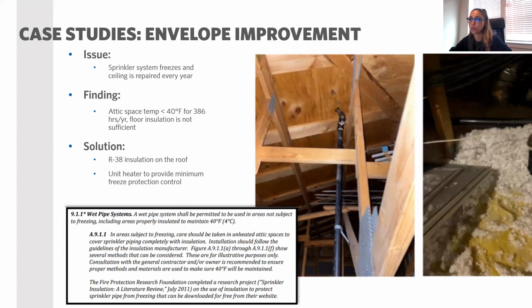So we recommended going with R38 insulation, which is the current code requirement for that climate zone. I think even R21 should be fine. But they will need some type of space heater to make sure that space never goes below 40 degrees. So this ECM itself, putting in the R38 insulation, is not going to pay back in maybe 30 years, because the impact it will have on the heating and cooling load will not be significant. And just having that insulation for the whole roof will be very expensive. But in order to comply with the code and not have these maintenance problems, they should have this solution.